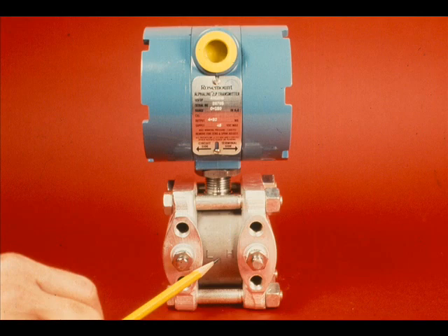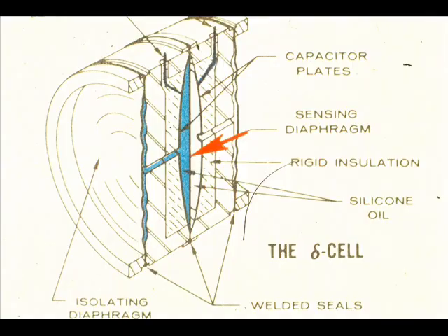The variable capacitance sensing element is located approximately midway between the high and low pressure ends of the differential pressure chamber. This is a cutaway view of the Rosemount Delta cell. Note the sensing diaphragm — it is a stretched spring element that deflects in response to differential pressure.